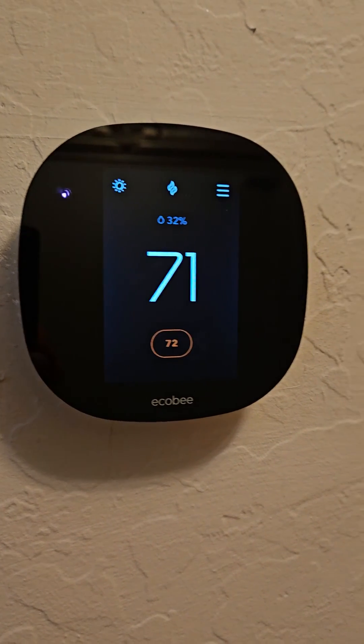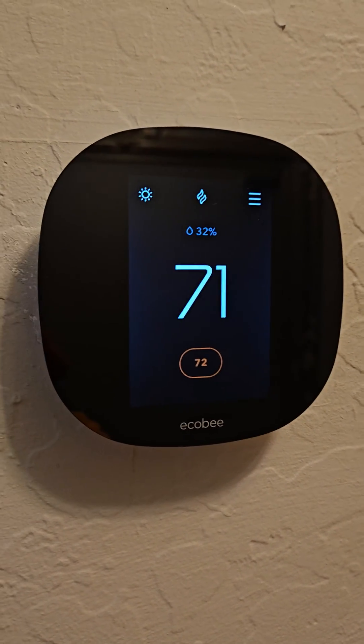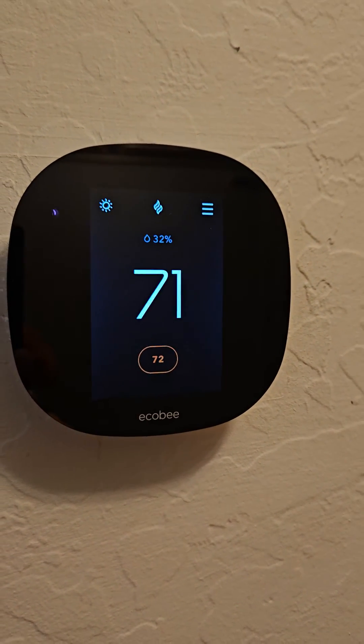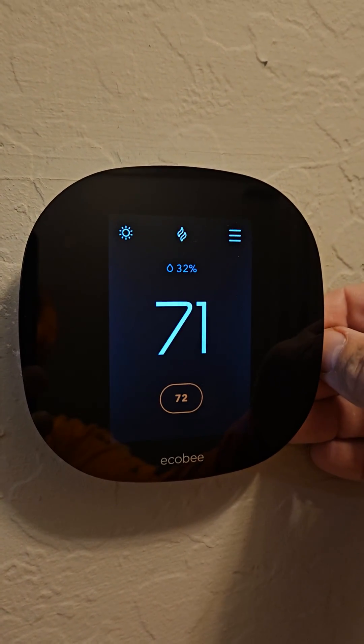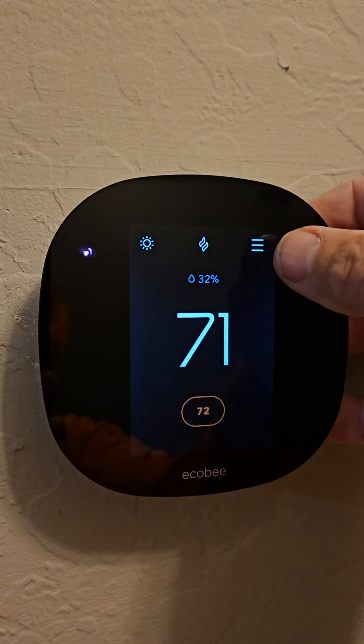If you're having problems with your Ecobee and your heat pump at 35 degrees, this is something that could be affecting it. It's a default value on the Ecobee. If it's not running in the mornings when it's really cold but then kicks on after a little while and is working fine, let me show you.